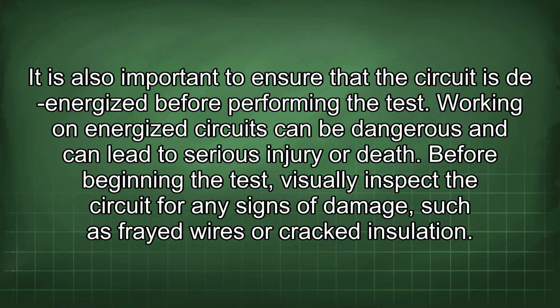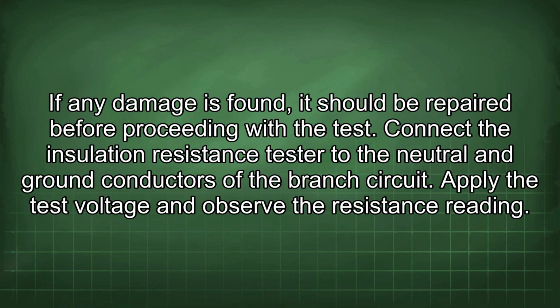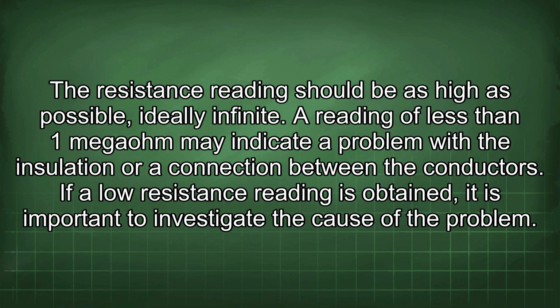Before beginning the test, visually inspect the circuit for any signs of damage, such as frayed wires or cracked insulation. If any damage is found, it should be repaired before proceeding with the test. Connect the insulation resistance tester to the neutral and ground conductors of the branch circuit. Apply the test voltage and observe the resistance reading. The resistance reading should be as high as possible, ideally infinite. A reading of less than 1 megaohm may indicate a problem with the insulation or a connection between the conductors.